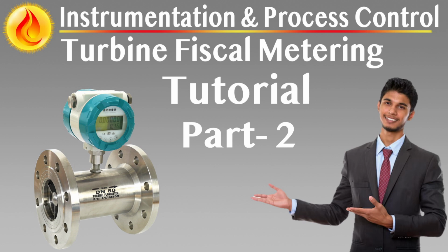Each stream typically has its own microcomputer to handle pulse counting, flow calculations, and local diagnostics. A central station microcomputer aggregates all stream data, interfaces with operator terminals, and communicates with the supervisory control systems, e.g., SCADA/DCS. The prover microcomputer manages all proving cycles, K-factor computation, and sequencing. While combining these functions into fewer devices may be considered for efficiency, it is only acceptable if availability, redundancy, and regulatory requirements remain fully satisfied.